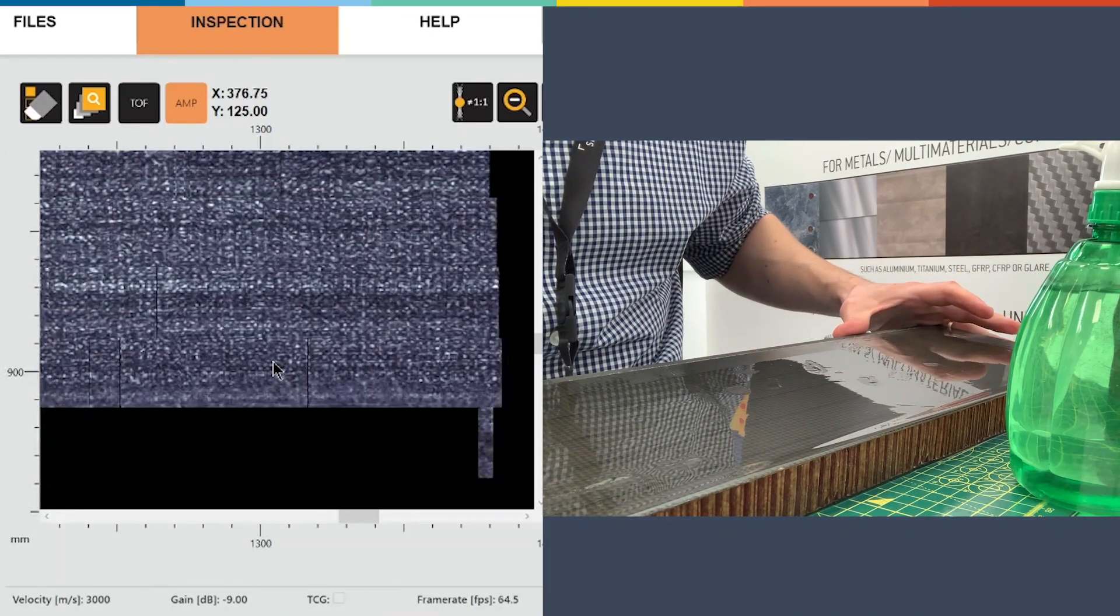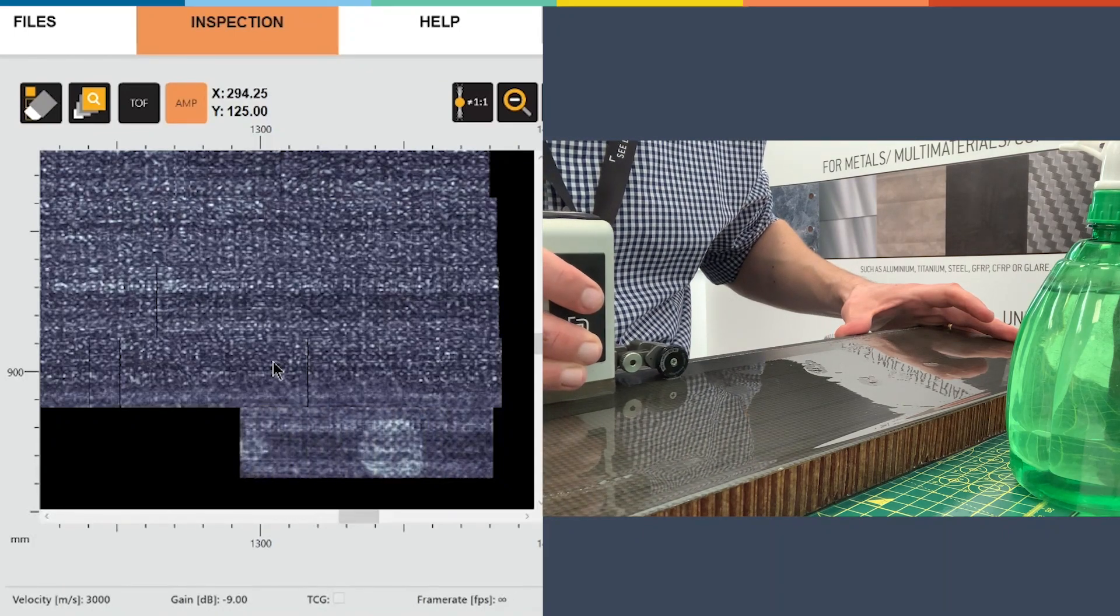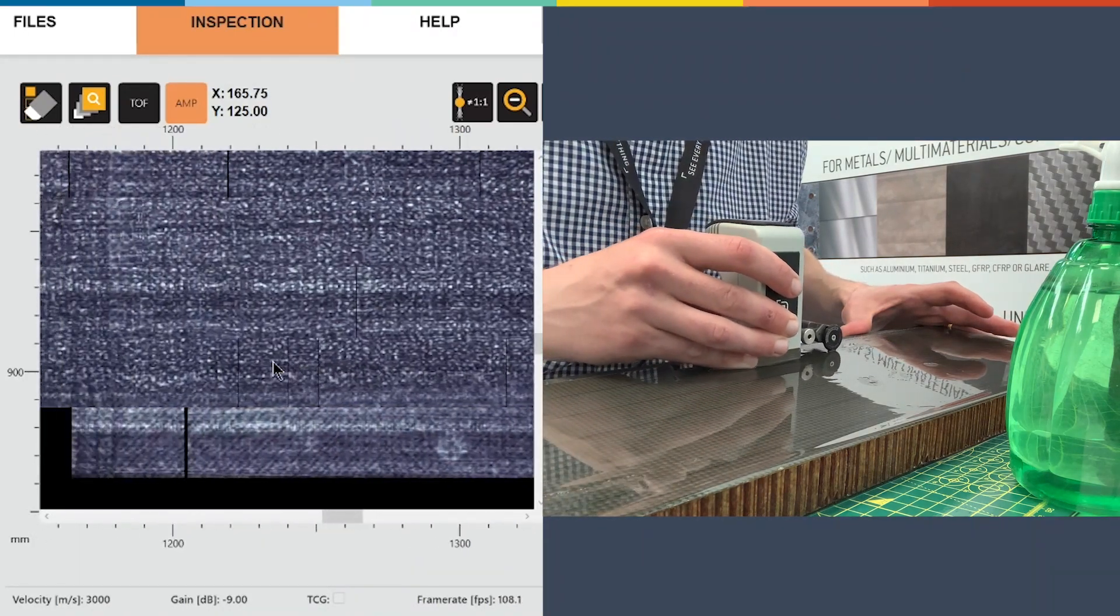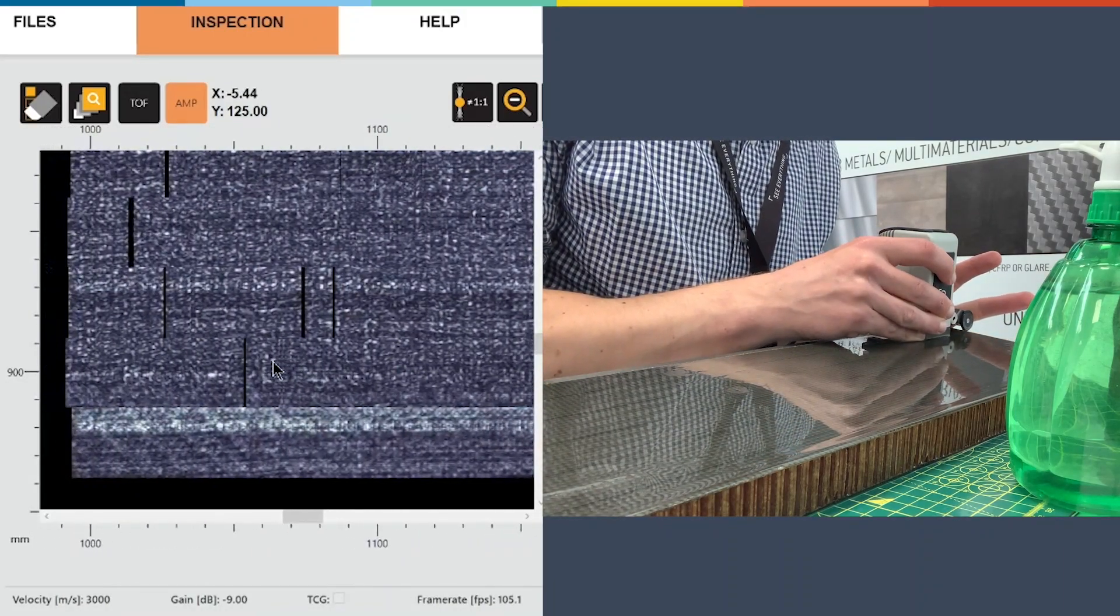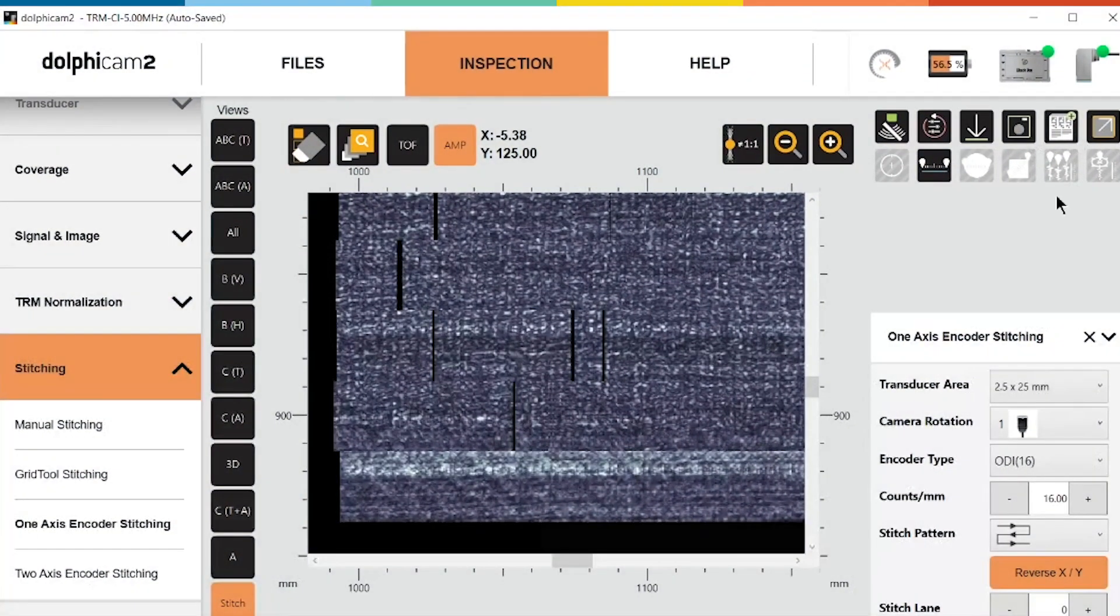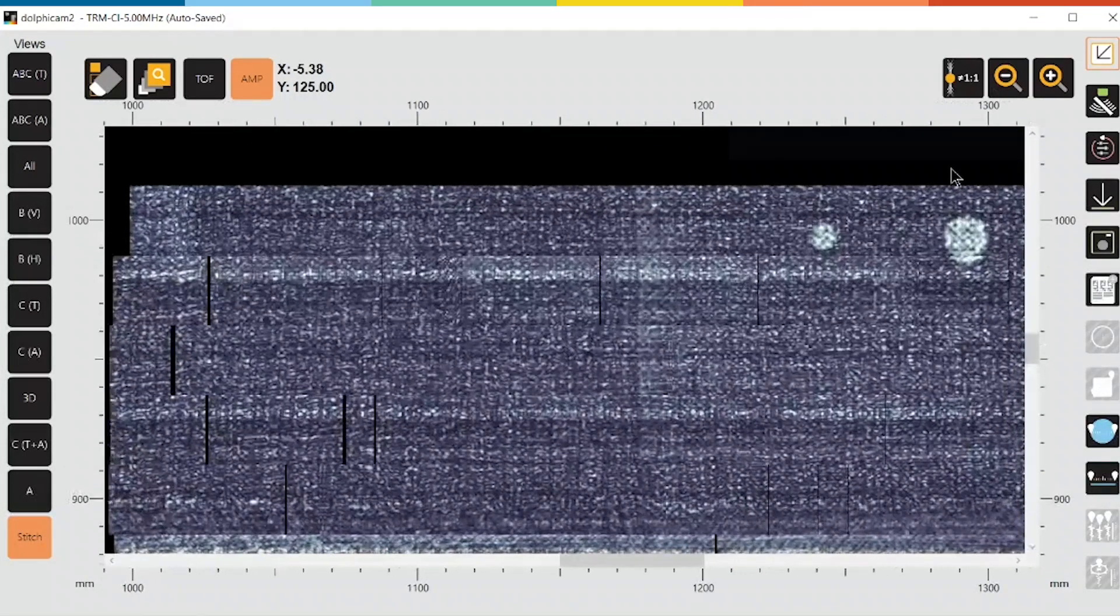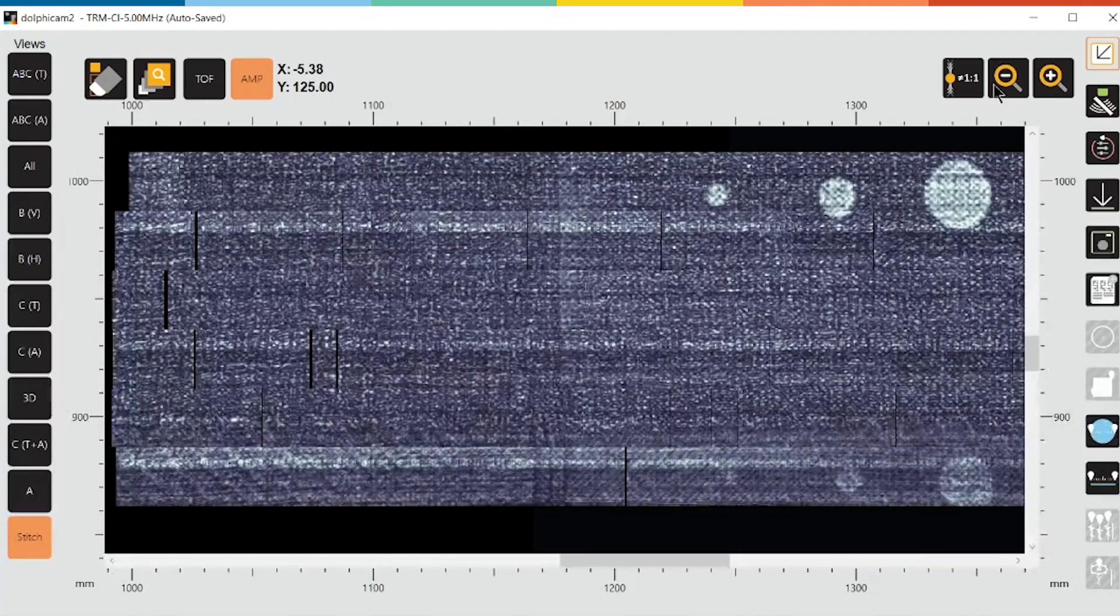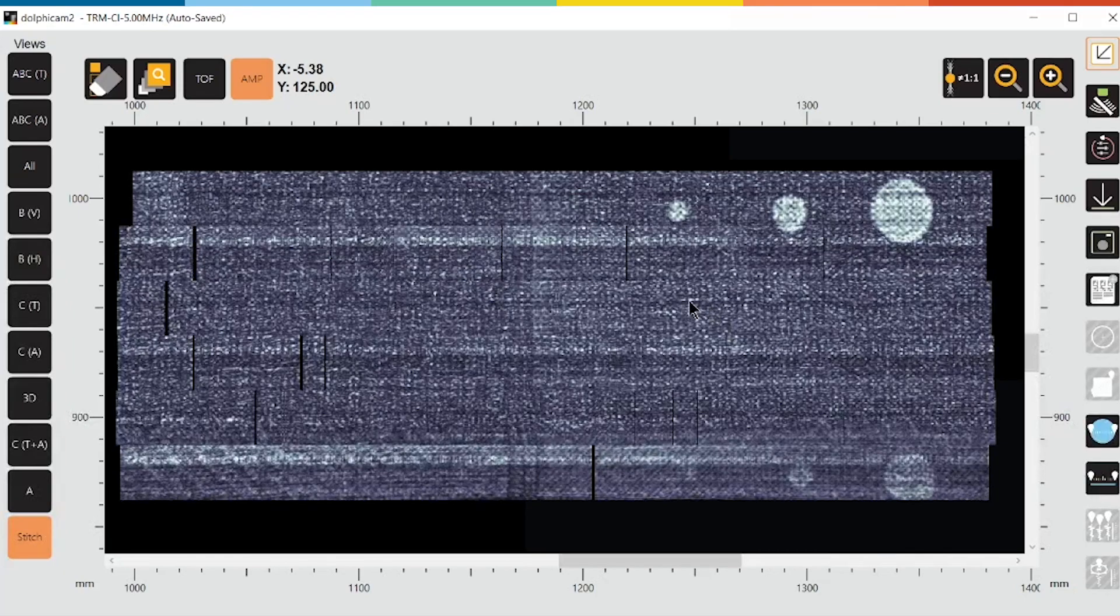Going down to the final line and there we have it. Now I've finished I can come into my full mode. I can arrange this so that I have the full C-scan in display and I've acquired this whole area without touching the software once through using that button on the TRM itself. We're just looking at the amplitude at the moment.